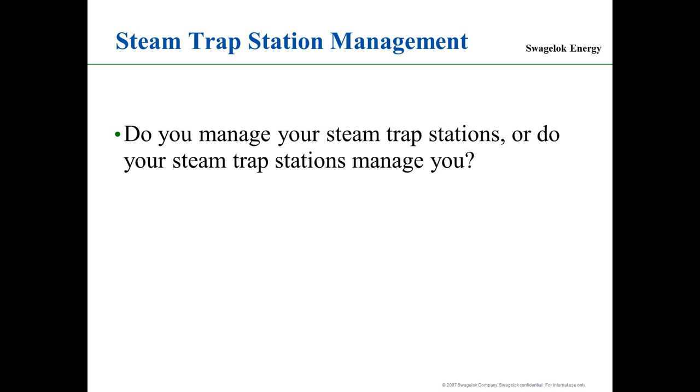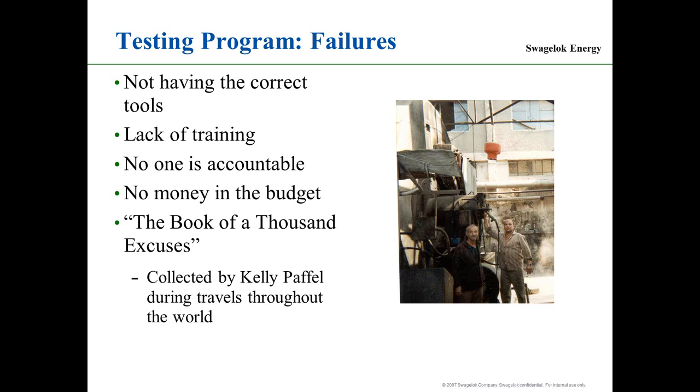What you have to do is establish what I call a management program. Certain steam trap stations are tested every 30 days, and some are tested every 2 years. So it's about prioritizing which ones I really have to watch, which ones can cause me production problems and things like that.